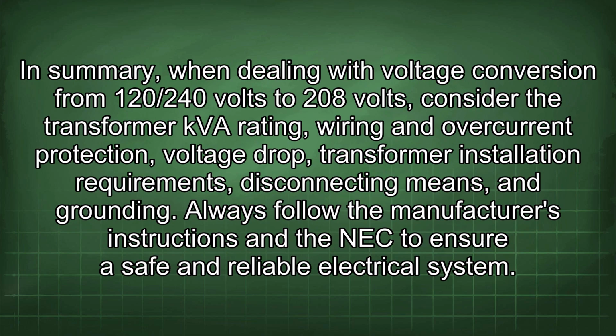In summary, when dealing with voltage conversion from 120/240 volts to 208 volts, consider the transformer kVA rating, wiring and overcurrent protection, voltage drop, transformer installation requirements, disconnecting means, and grounding. Always follow the manufacturer's instructions and the NEC to ensure a safe and reliable electrical system.